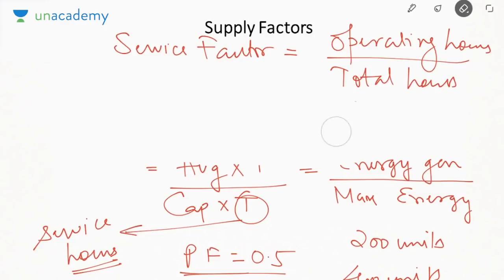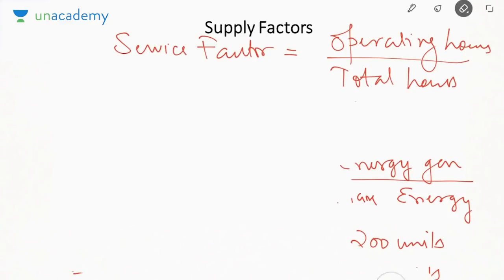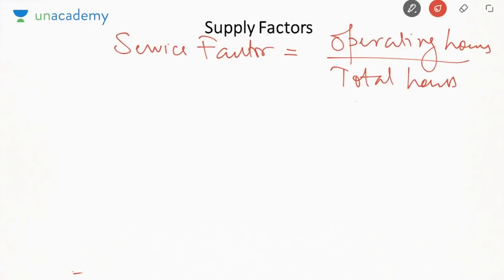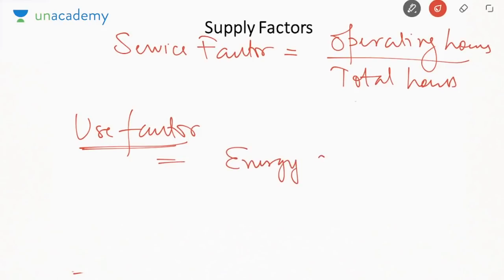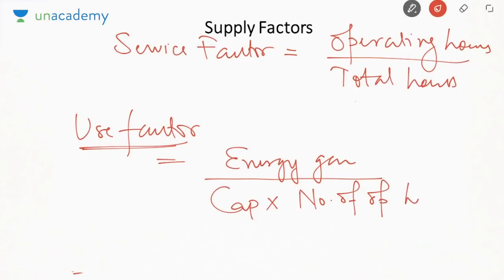And the last factor that is connected to the plant is the plant use factor. Plant use factor is energy generated, that is average demand into total duration, divided by capacity into number of operating hours. That is your plant use factor. So it is the energy generated by the energy that could have been generated.